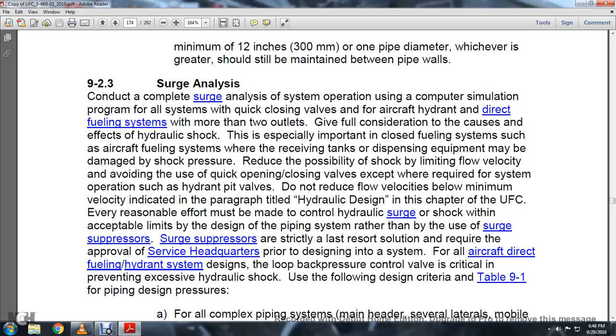For all complex piping systems with main headers, several laterals, and mobile equipment, employ computer modeling techniques to determine the surge suppression that is required. Conduct a run at a steady flow condition to establish system flow rates for the scenario being modeled. After that, conduct a transient surge analysis, imposing the worst case operation conditions on the system. For the hydrant system, incorporate the use of a back pressure control valve to simulate the valves of the active modulating valve. If acceptable peak pressures are exceeded, discuss the results.